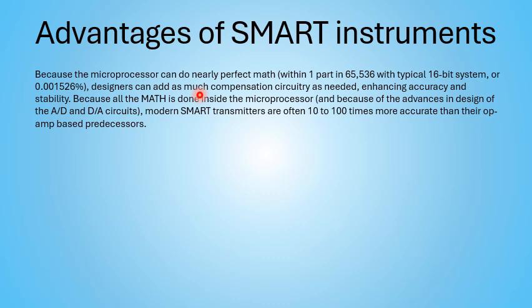So that microprocessor math, it's ones and zeros, and it's either on or it's off, and it has all these algorithms to keep it from getting confused and being almost or kind of sort of, which analog does, right? Analog drifts, it's not exact. So for that reason, those calculations are incredibly accurate and stable. They don't have those drift and other problems. That is the biggest benefit of the smart instruments or using a microprocessor, is that all of the math is as perfect as you would be able to even realize. They're typically from 10 to up to 100 times more accurate than the op-amp based predecessor, which is a remarkable contrast, and yet a lot of times, like I said, it's not even factored into your maintenance programs.